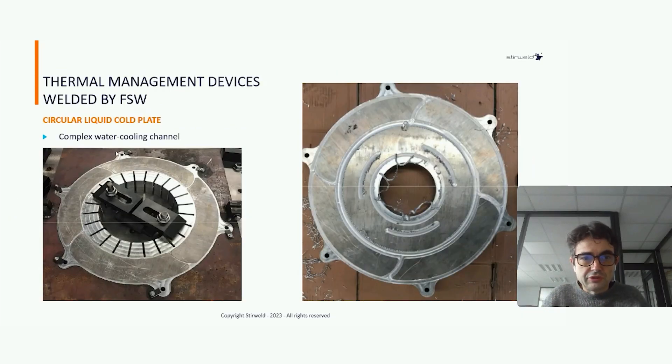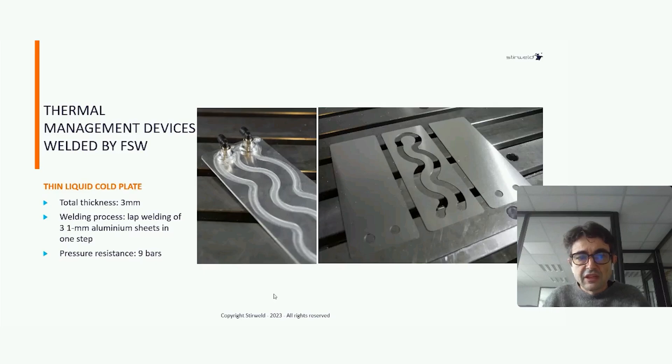Here is another example of a complex water cooling channel — cylindrical, but with a flat welding surface. This is a very thin cold plate; we start from three sheets of one millimeter thickness, laser cut and stacked together. The friction stir welding tool goes through the two top sheets and welds with the bottom sheet, so in one welding pass we get this very thin cold plate — three millimeters total thickness — which withstood a pressure burst of nine bars.